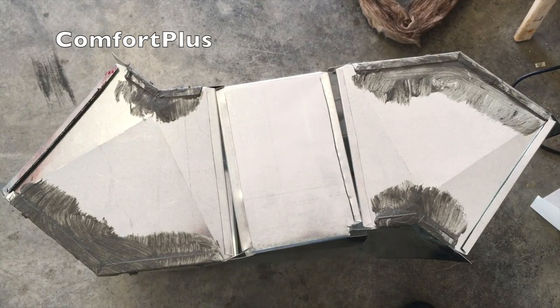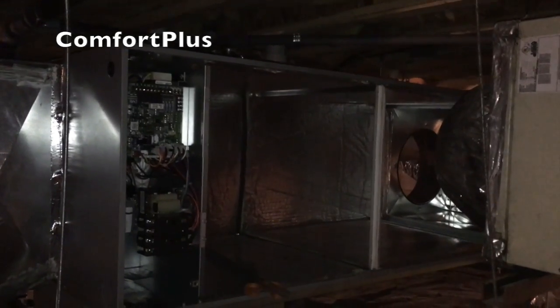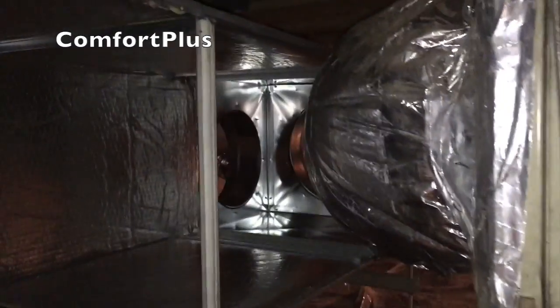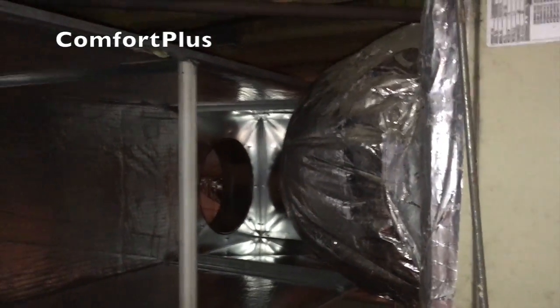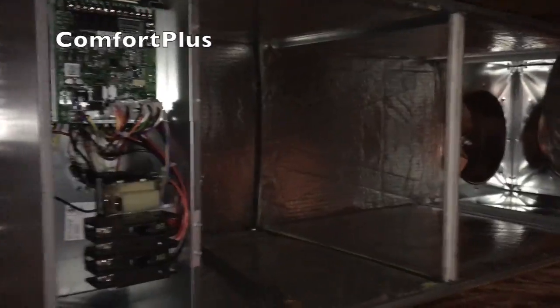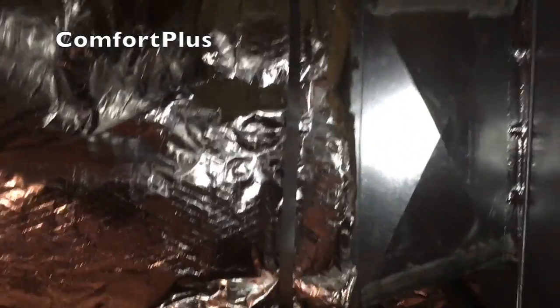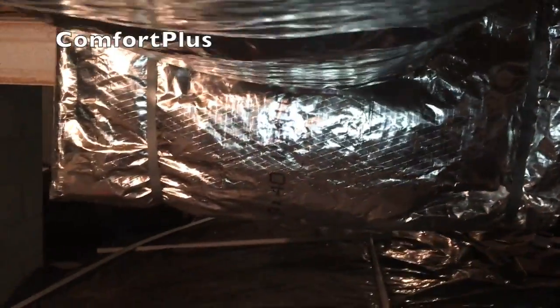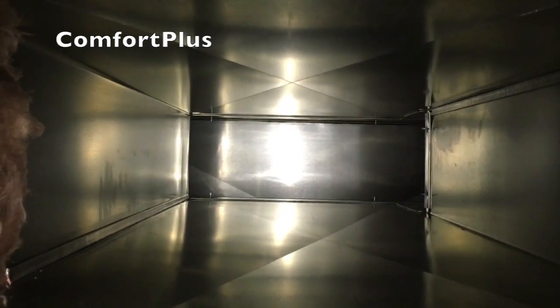Okay, got the new air handler hanging here right next to the old air handler. I'll have to take this one out before I can put my coil in and stuff. It's just too tight to do anything. So got this big piece of trunk under here and tied to the air handler and tied to the duct on the other zone. This is coming toward me.